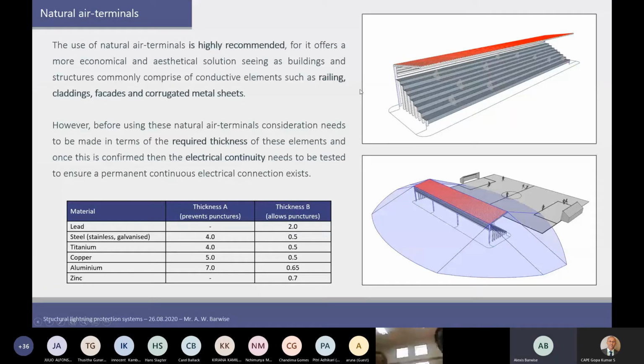Looking at the same structure, let's apply what we've just learned. Air termination means we have to intercept this, right? So we read from the standard that the use of natural terminals is highly recommended, right? Because it is obviously giving us a more economic and many times a more aesthetic solution. It even recommends us to use this, but we've just got to ensure one thing, and that is that the thickness of the natural air terminals has to be a certain value. And here we see the standard guides us again.